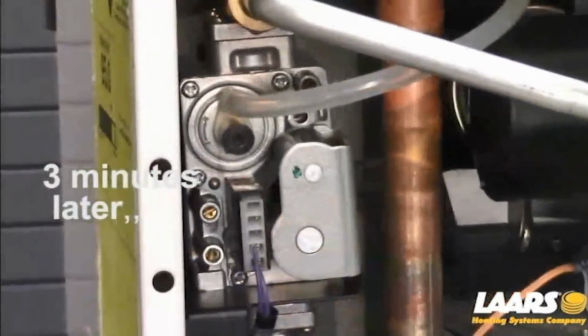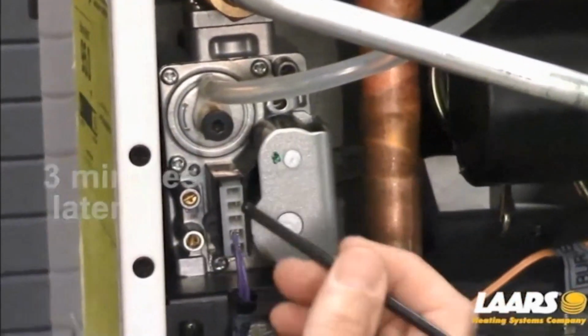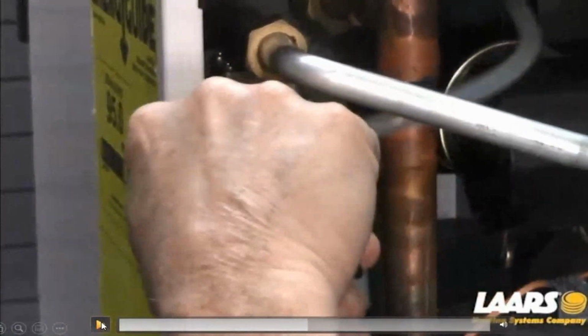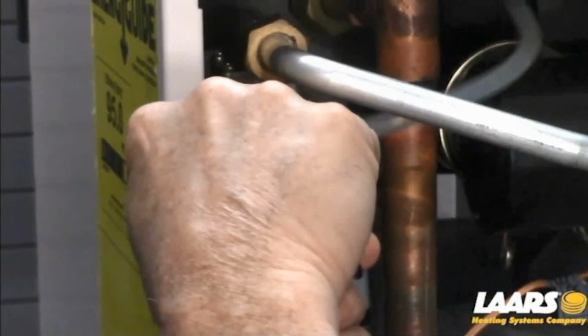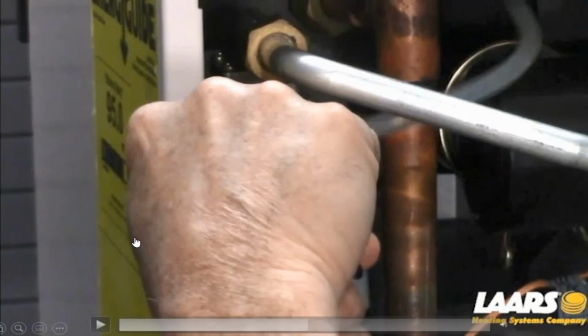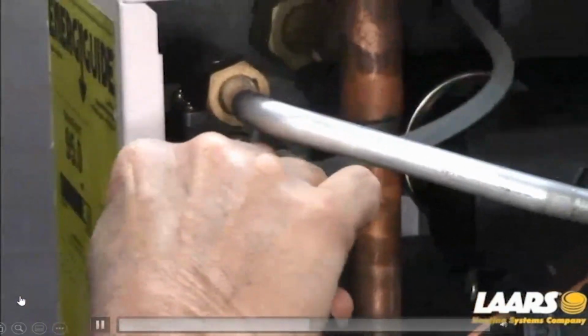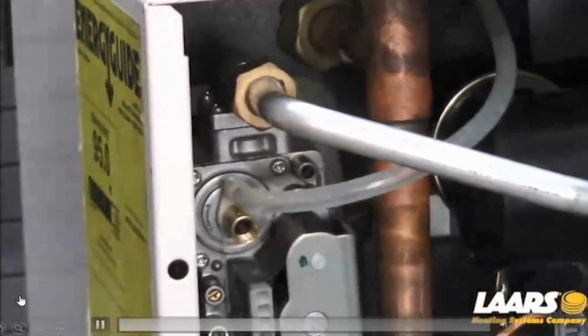So what we want to do is make a gas valve adjustment under this cap. So I'm going to remove the cap. It's a number 4 millimeter Allen key. Now, early version, the cap was a 4 millimeter Allen key. The later versions are a Torx bit. And I believe that Torx bit is a number 20 Torx bit. And now we can make an adjustment.